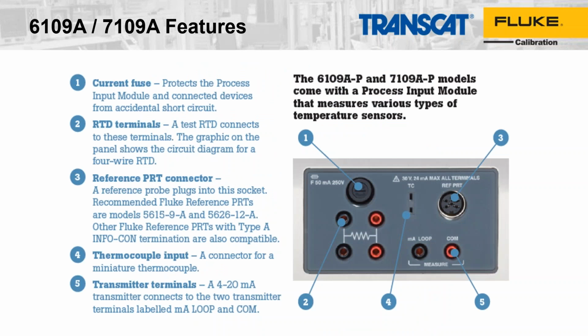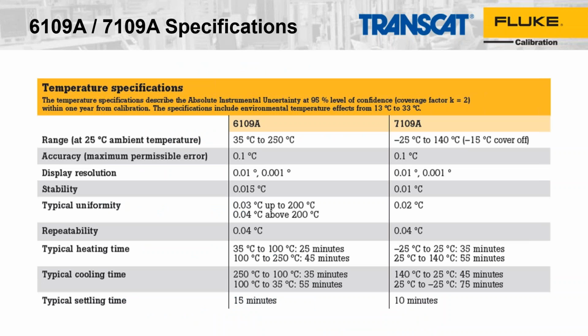Okay, so typical heating time examples here: going from 35 to 100, about 25 minutes. Going from 100 to 250, 45 minutes. Cooling time, so this is the heat-only bath: going from 250 to 100, 35 minutes; 100 to 35, 55 minutes. Typical settling time is about 15 minutes for the 6109A and 10 minutes for the 7109A. Sorry, I was just looking to see if there's any other information on the next slide. So that gives you a general idea of how quickly these will change from one temperature set point to the next.